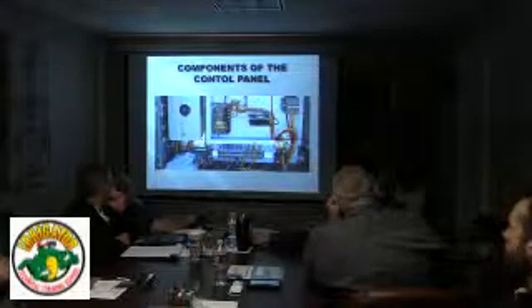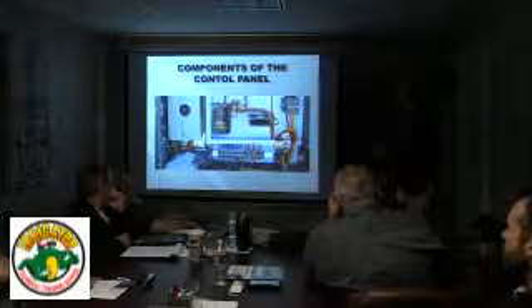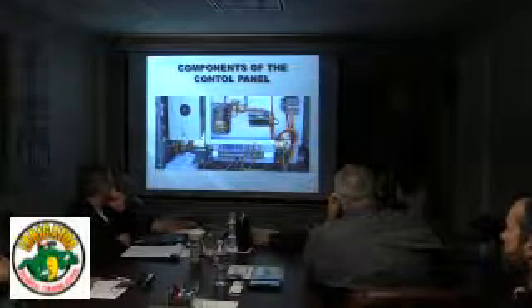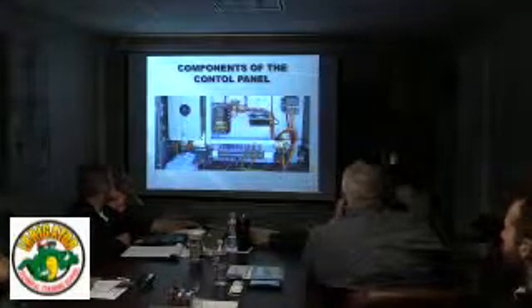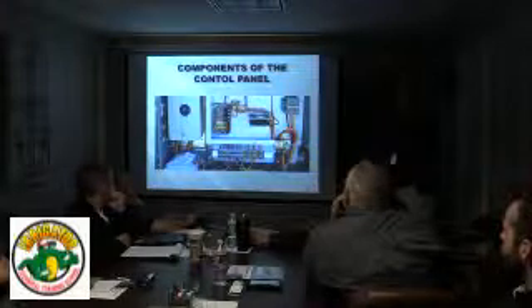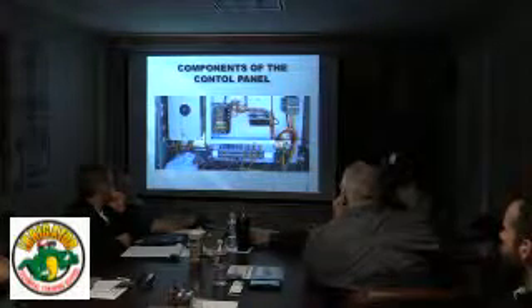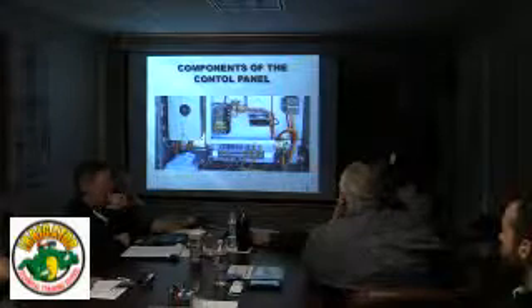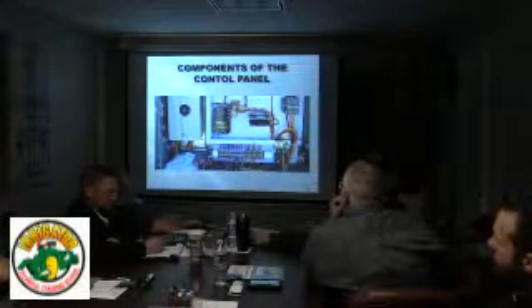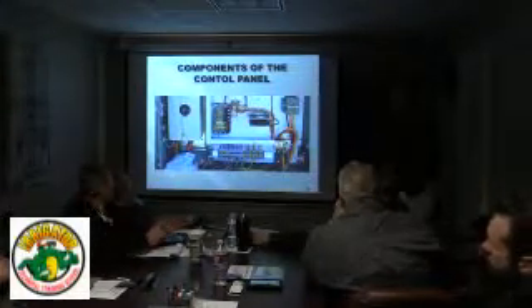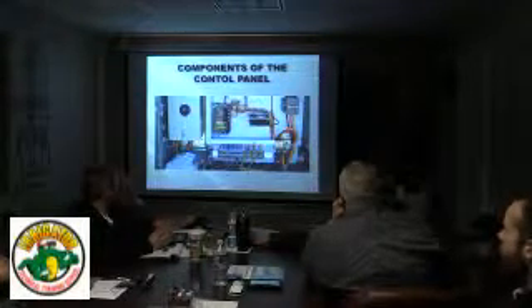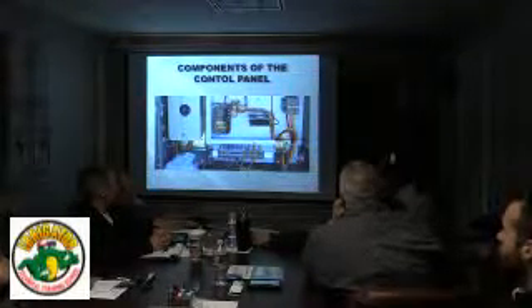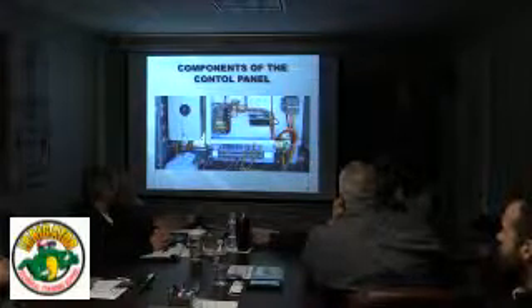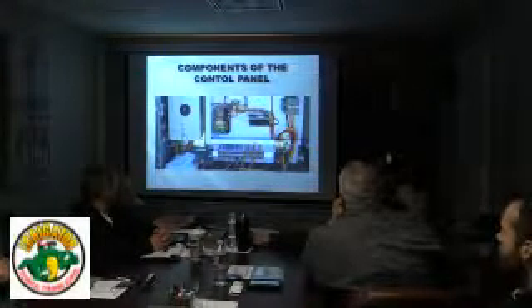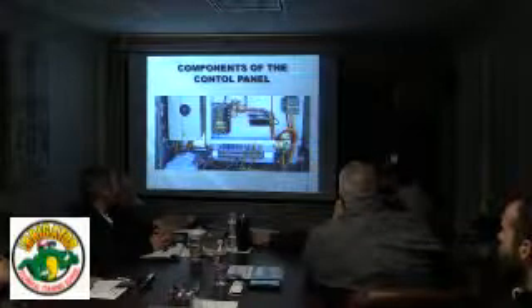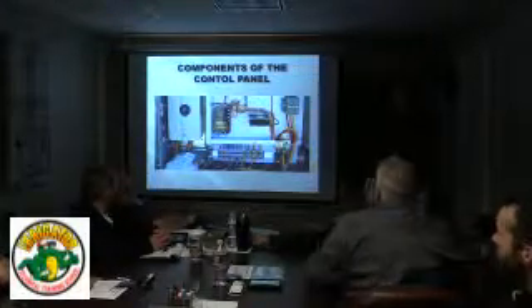Then you also notice here that we have a splice block. We put this in here because it's easier to connect motor leads up to this. A lot of times the motor leads are larger, especially if they have to be run a long distance. You have to take the cover off the drive and put them in. So we'll supply a splice block like this in a lot of cases. But just note that there's always a label at the bottom down there that will tell you it's motor output. So just a little more convenient to hook the motor leads up to here.